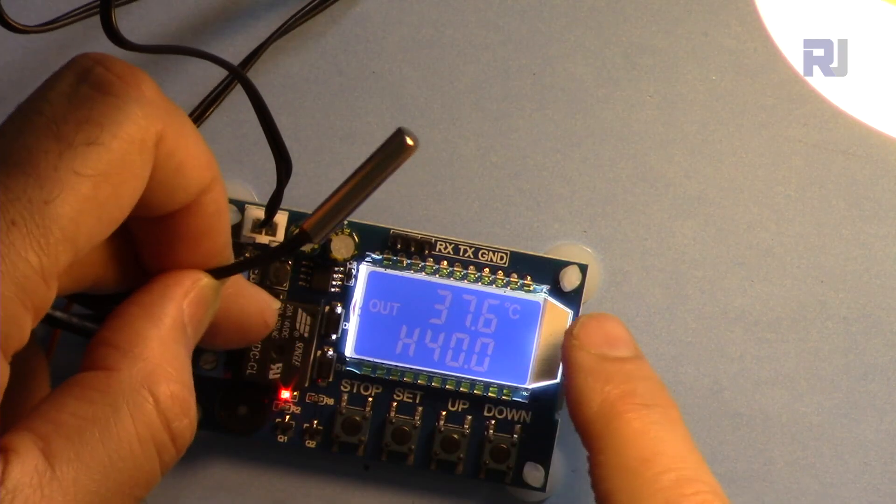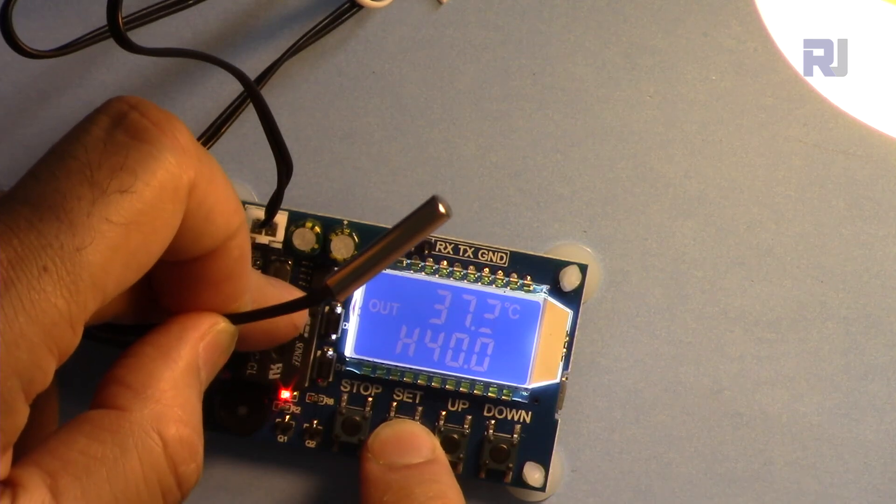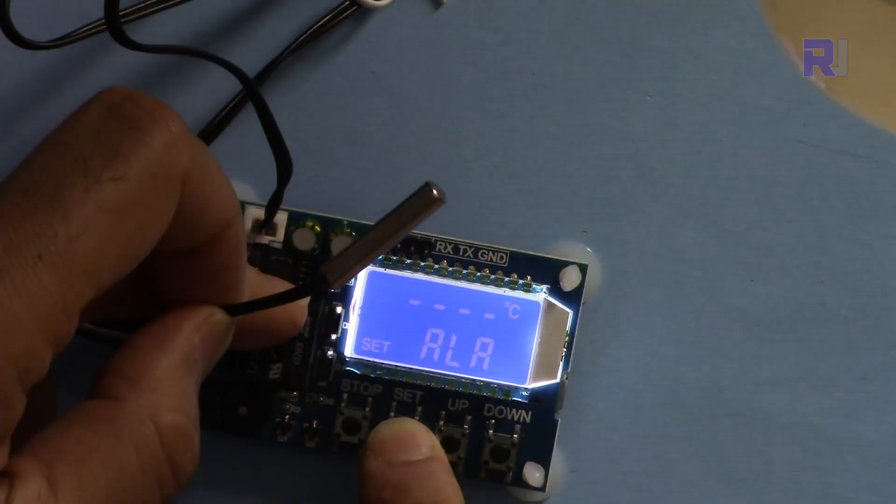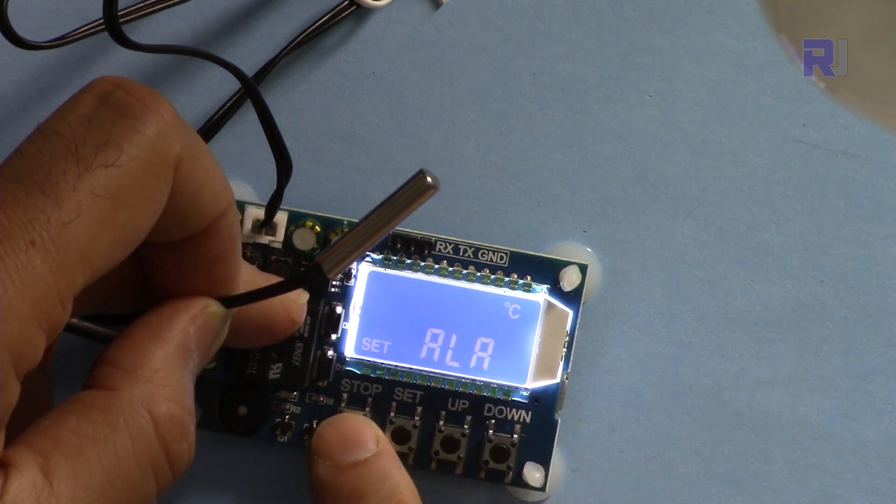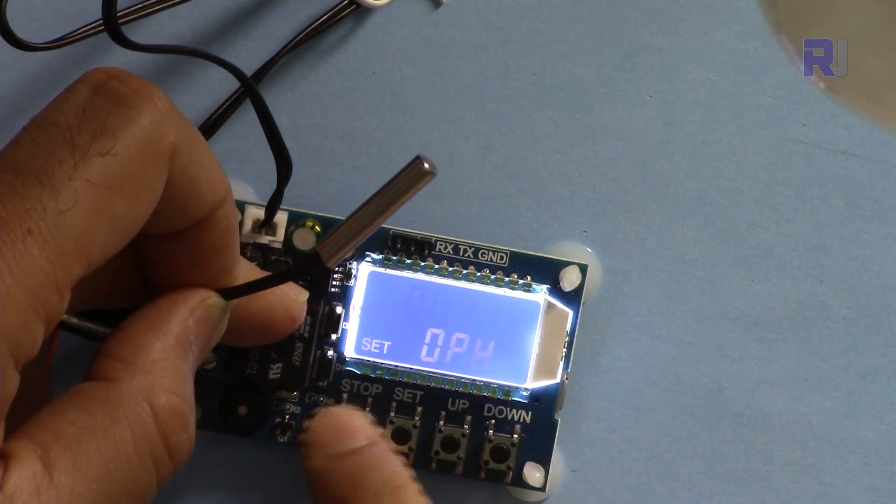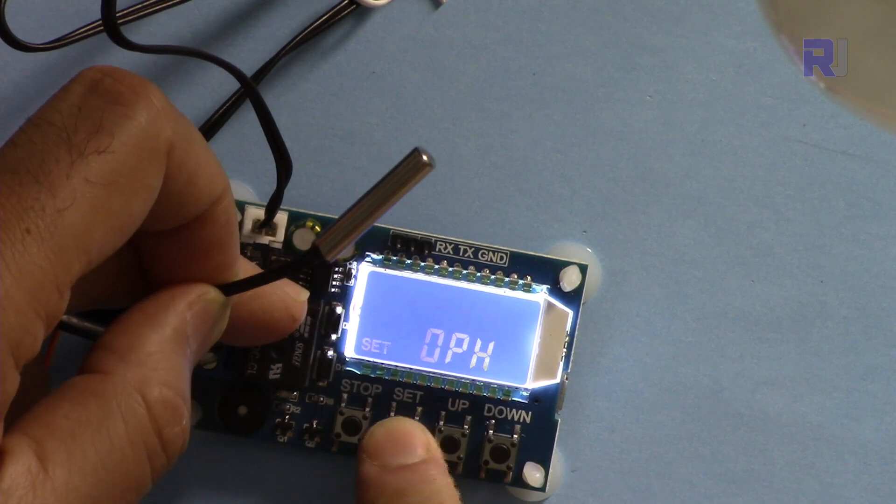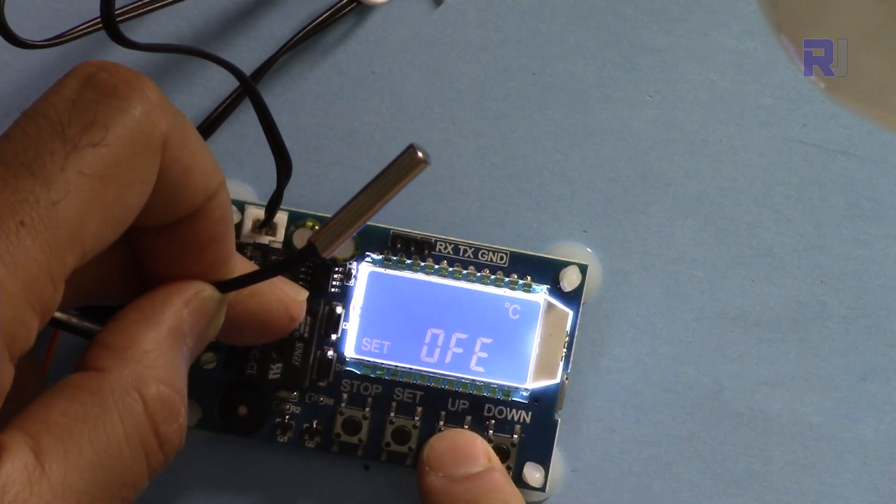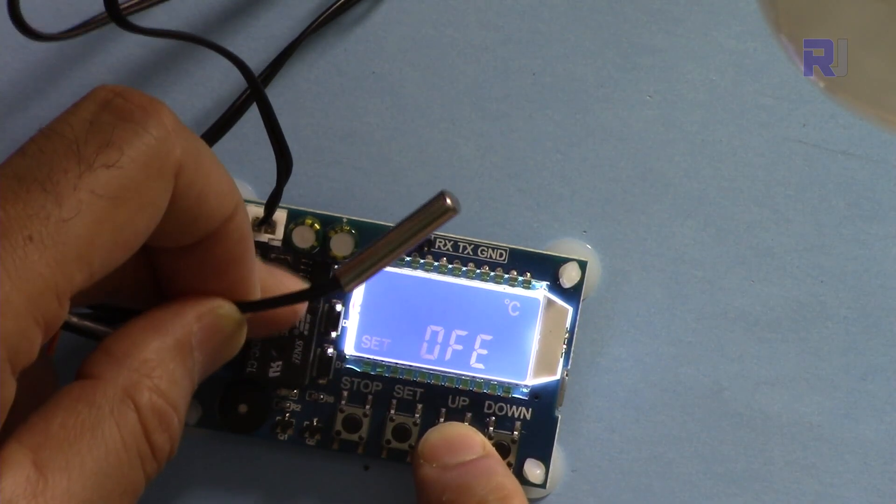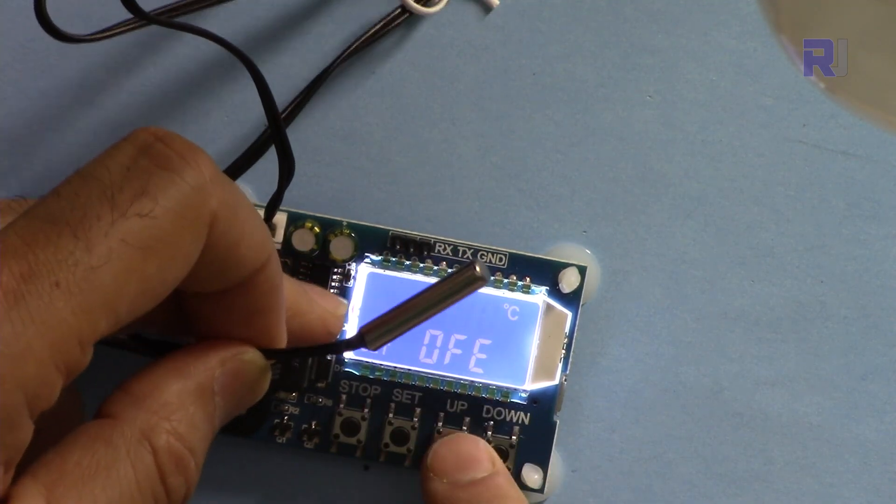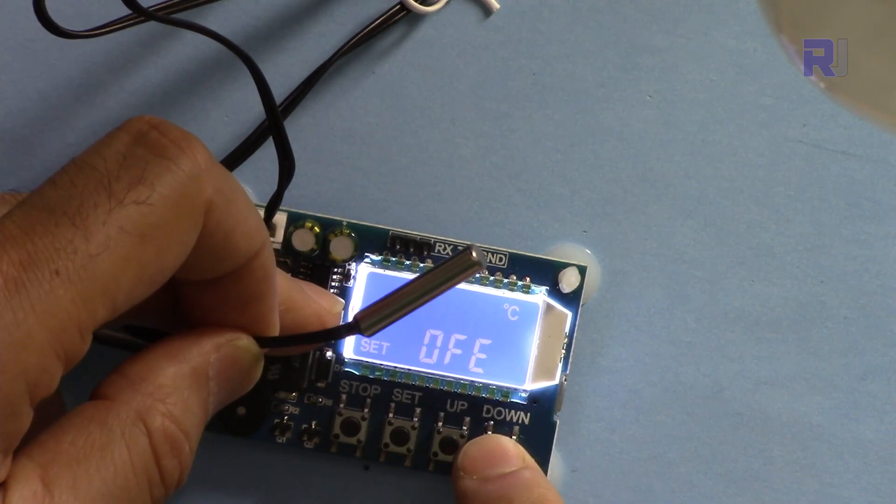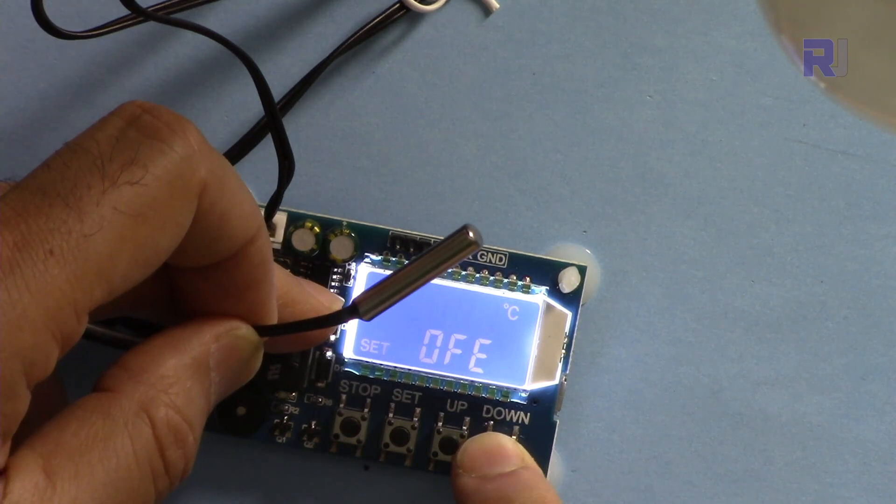The other feature that we have is if I press and hold this for a few seconds, ALA, and then press this again, OPH. Let's turn this off. And if I press this again, offset. That offset is for the temperature. If your sensor is sensing incorrectly you can reduce it or you can increase it 0.5 or whatever or even up to 10 degrees Celsius you can add or reduce. I'm not going to do it.